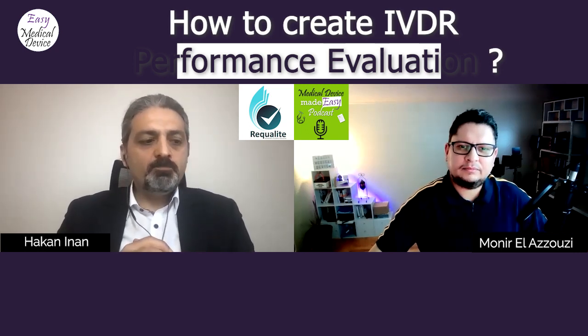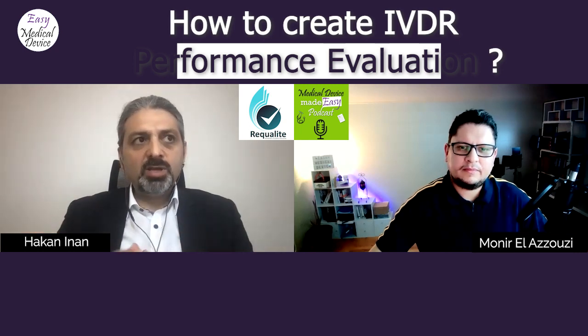Yeah, Münir, let's give some background information first. When you look at the regulation, the performance evaluation as a term has been mentioned 121 times. When you compare this to the clinical evaluation, it's very comparable to clinical evaluation in MDR. So we can see that the emphasis, the philosophy of the lawmaker, is on the performance evaluation. Now, Article 2 in IVDR gives you the definition of different terms. There, performance evaluation is described as the assessment and the analysis of the data to establish or to verify scientific validity, analytical performance, and clinical performance of the device. So this is the official, by-law definition of the performance evaluation.